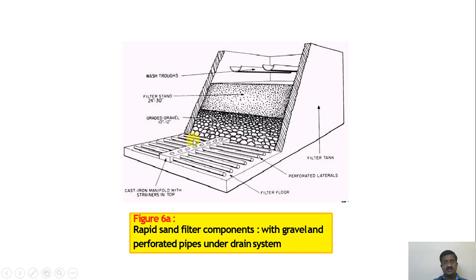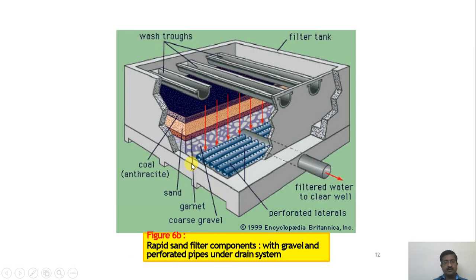This figure shows the rapid sand filter components with the gravel and perforated pipe under drain system. During backwashing, reverse water is sent through the layers, which removes dirty water via wash troughs. During filtration, the perforated pipes carry filtered water to the clear water zone. The wash water troughs and under drain system components are visible in the pictorial view.